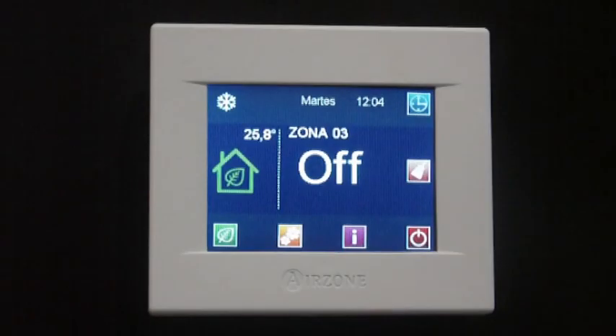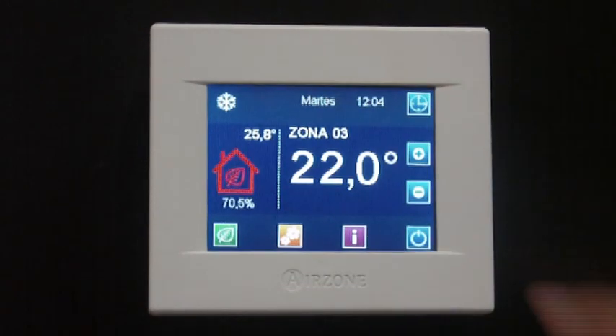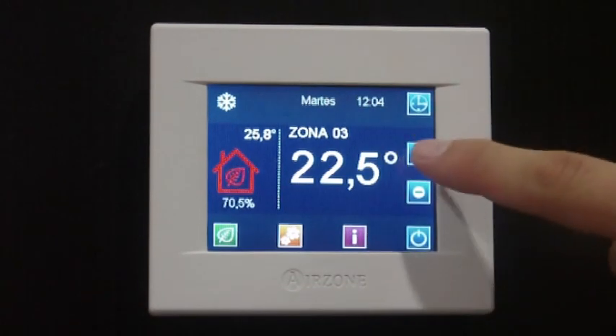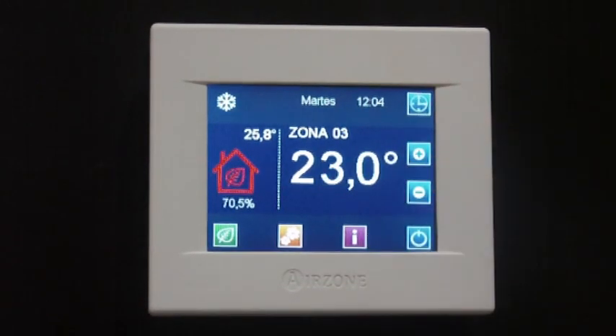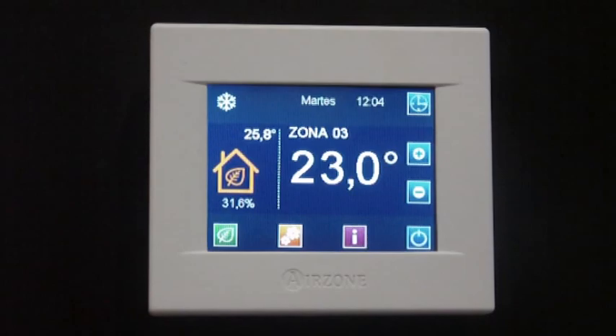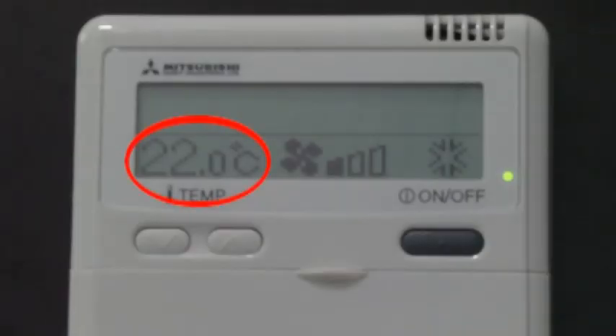When modifying the zone set point temperature, the communication gateway will detect this change and will also modify the set point temperature in the AC unit. This way the system works more time in partial load rate, making the installation more efficient.